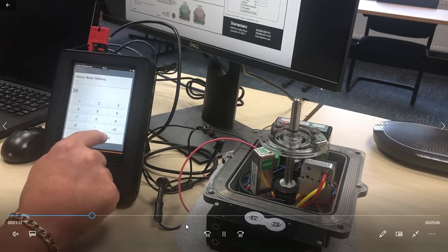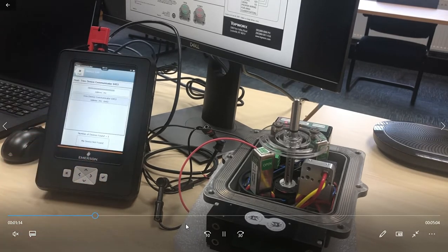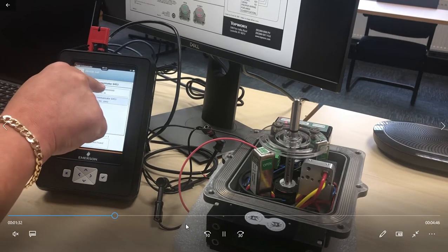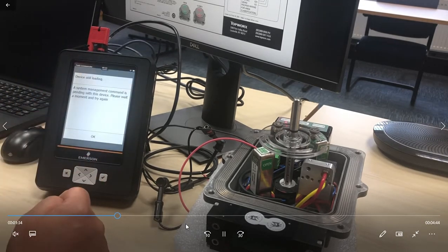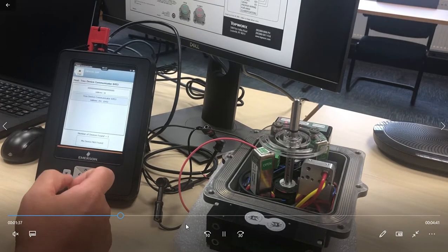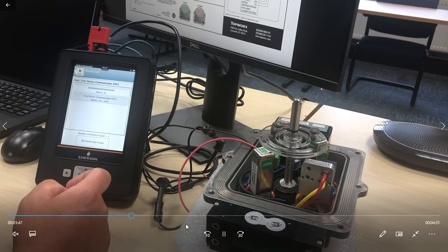There is a number of parameters from 25 to 35 that you can use. In this case, we're changing to 34. In any changes, it needs to poll directly to the device and then back to the TREX, so there is a little lag in this period. And as you can see now, it's disabled the 251 and enabled the 34, but immediately it's not available because again it has to poll the information and ensure that it's connected to the device correctly. So as mentioned, this takes a little bit of time.